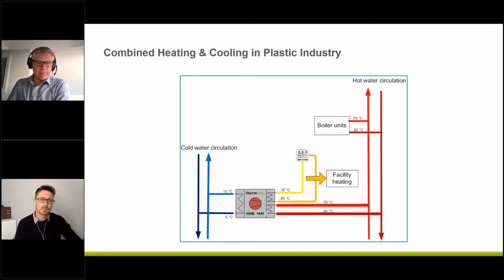Yeah, well, obviously, first of all, they have to be qualified technicians to work on high pressure systems. First of all, the ratings of the pipework as well, it's all coded welding as well. So the fittings are rated for the high pressures. Again, it's very similar to existing chillers, so there are no additional different measures. But one thing that is important to say is that it does come with a gas detection system. So in the event of a gas escape, it'll tie into the building management system or evacuation system, depending on the size of the plant room as well. That should be looked at at the time of installation.